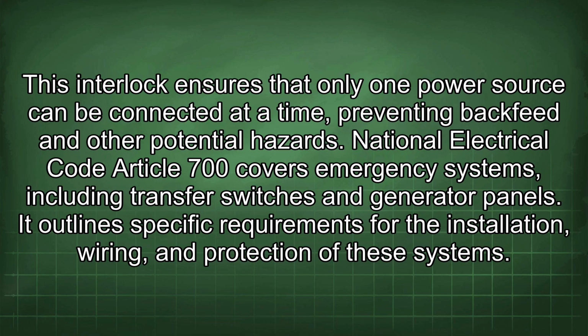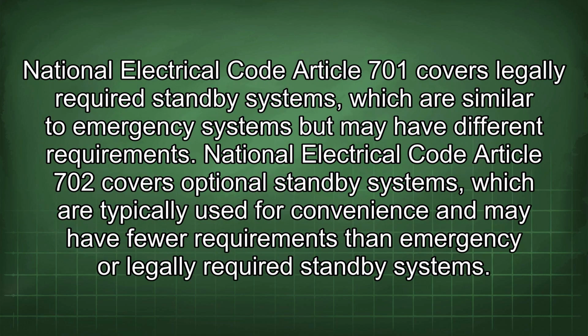National Electrical Code Article 700 covers emergency systems, including transfer switches and generator panels. It outlines specific requirements for the installation, wiring, and protection of these systems. National Electrical Code Article 701 covers legally required standby systems, which are similar to emergency systems but may have different requirements. National Electrical Code Article 702 covers optional standby systems, which are typically used for convenience and may have fewer requirements than emergency or legally required standby systems.